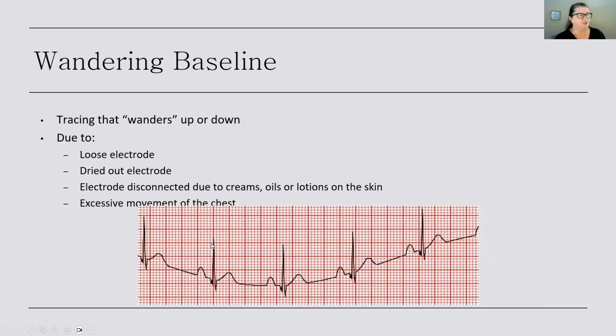Wandering baseline is literally a tracing that wanders either up or down like this. It doesn't go straight across. This is usually due to a loose electrode. Maybe the electrode is dried out. Electrodes do expire, so you have to pay attention to the expiration dates on those. If they're dried out, they're not going to stick well, they're not going to conduct well. It could be that an electrode got disconnected and you can't really see it, maybe because the skin was really oily or there's lotions or creams. In that instance, of course, just take the electrode off, clean the area really good with an alcohol prep, and then try to put a new one on. Or there could just be excessive movement in the chest. Like if they're breathing really heavily, that movement can cause a wandering baseline. So you just check all those things and make sure that you're good.